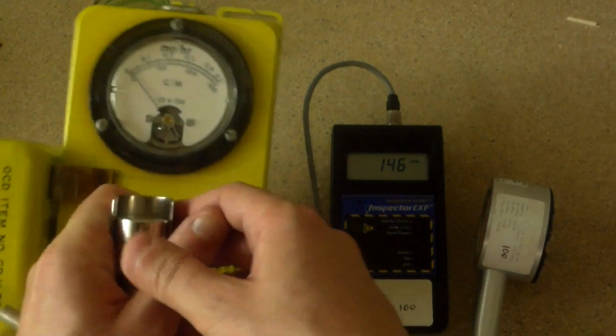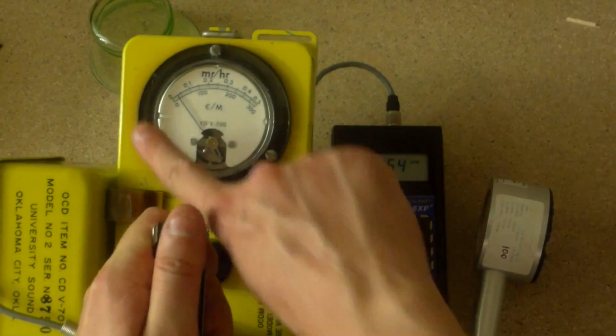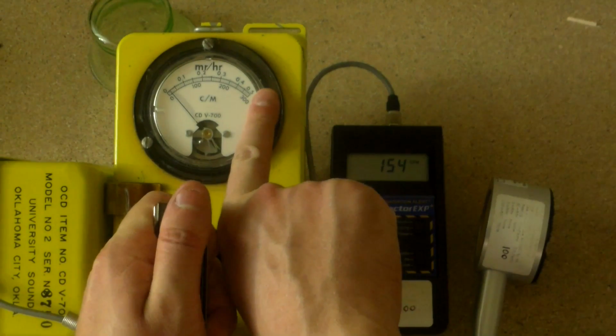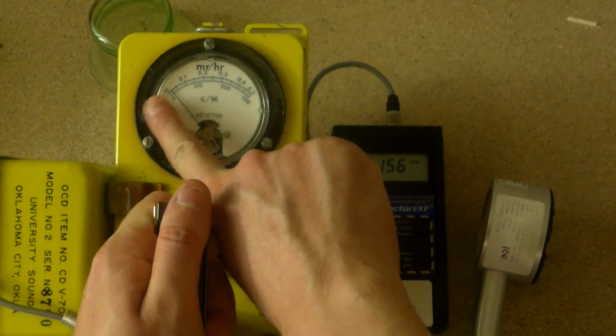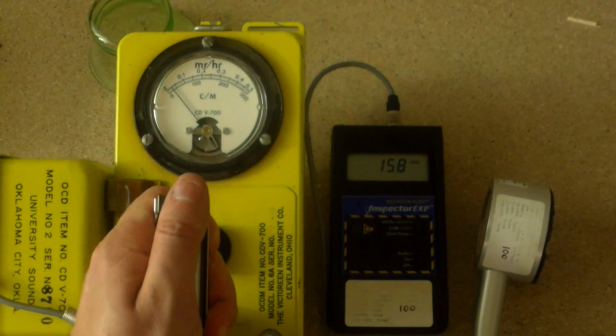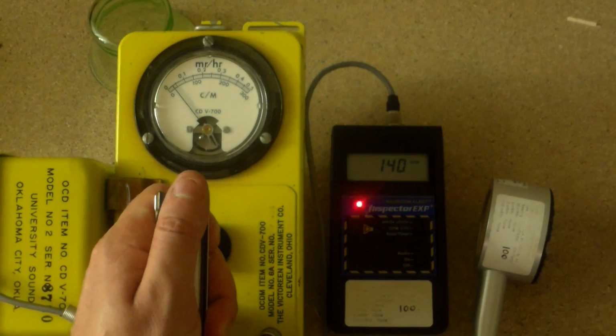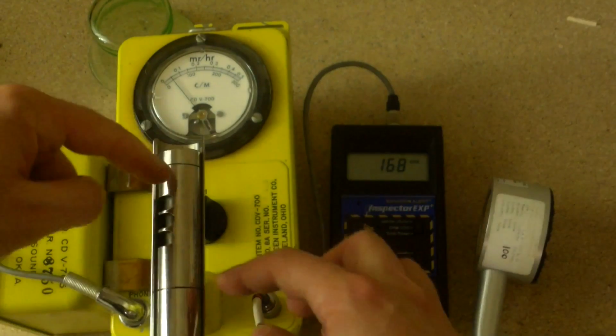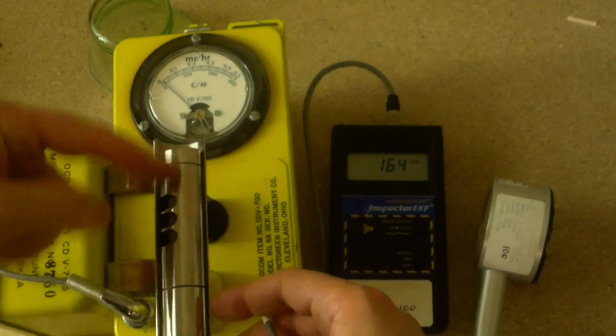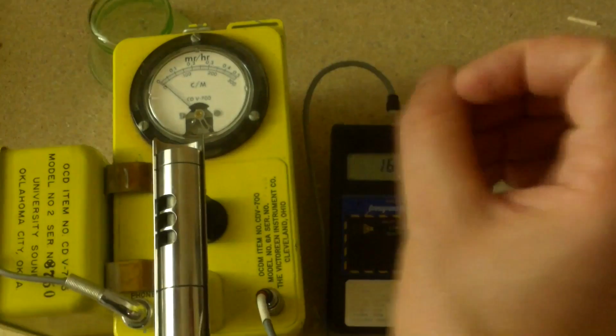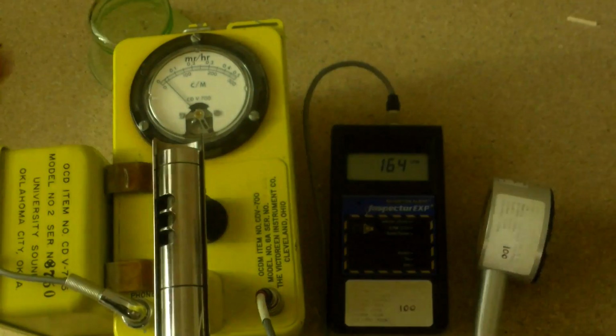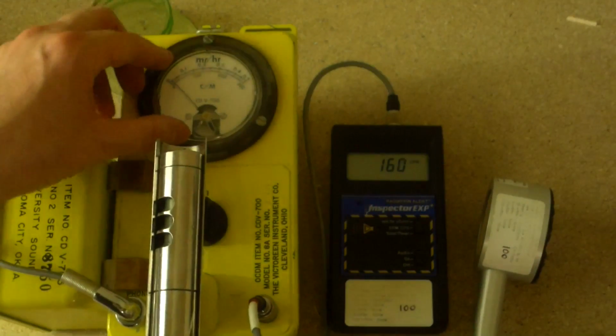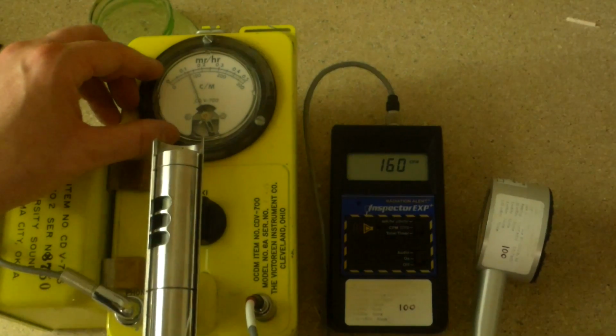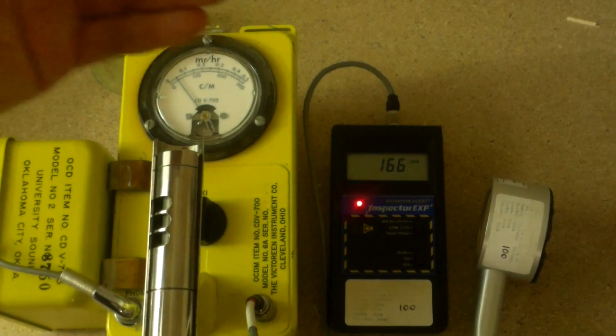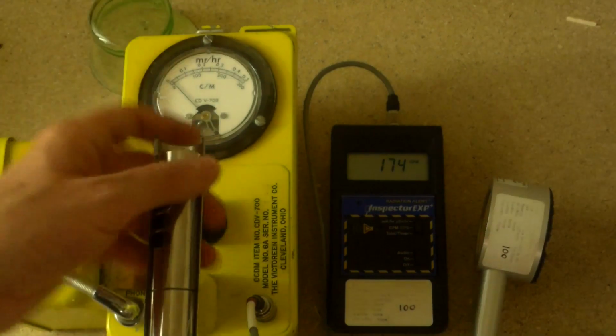How will these two detectors respond? Well, this one right here is an old detector built in ancient days of yore. It will fly all the way to the max reading and then it will slowly drift back down and stop. And you're going to think, oh, I must have hit an energy spike, but now everything's fine. It's just become overloaded. There's so much radiation that the tube is now conducting a continuous electrical circuit through it. Basically, it's not making ticks anymore. The ticks have just become a solid mass. As a result, this detector looks like it's showing you nothing because it is jammed, it is saturated. You could be exposed to a lot of radiation and have no idea that's happening.